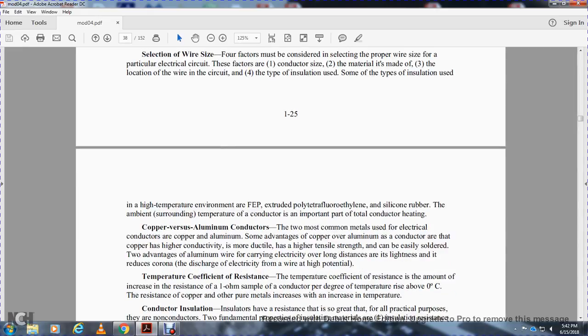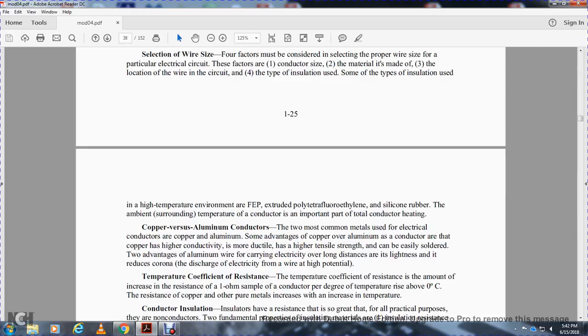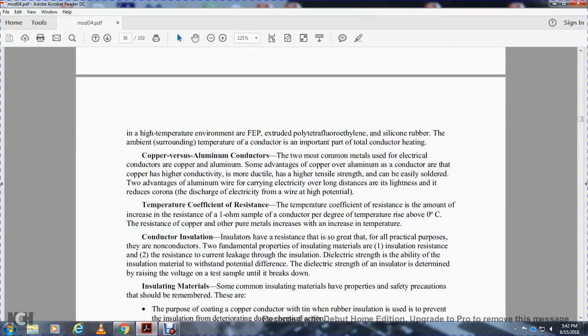Copper versus aluminum conductors. The two most common metals for electrical conductors are copper and aluminum. Some advantages of copper over aluminum as a conductor include higher conductivity, more ductility, higher tensile strength, and it can be easily soldered. Two advantages of aluminum wire include its ability to carry electricity over longer distances, its lightness, and reduced corona discharge on high-potential wires.